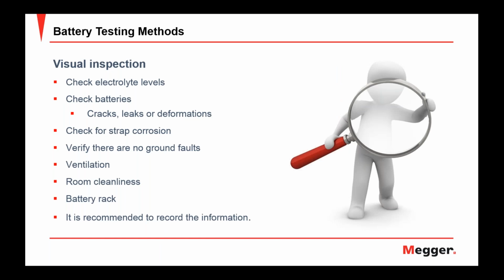Visual inspection is very simple to do, but it's something we really do need to do. We want to check things like electrolyte levels on flooded cells. Make sure it's within the proper limits. We don't want to overfill it or underfill it. We want to check the battery for cracks, leaks, or deformations. If we see a battery that's bulging, we're pretty well done at that point.